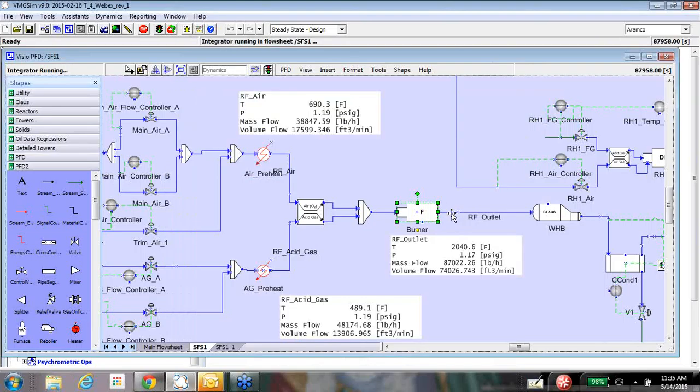And that's really helpful information because while we go for different scenario studies, it helps us to see what would be the pressure drop, what would be the pressure along the pipelines, and that eventually gives us an idea of what will be the velocity. Because many of our clients want to check all their guidelines during different scenarios, whether any guideline is violated or not.